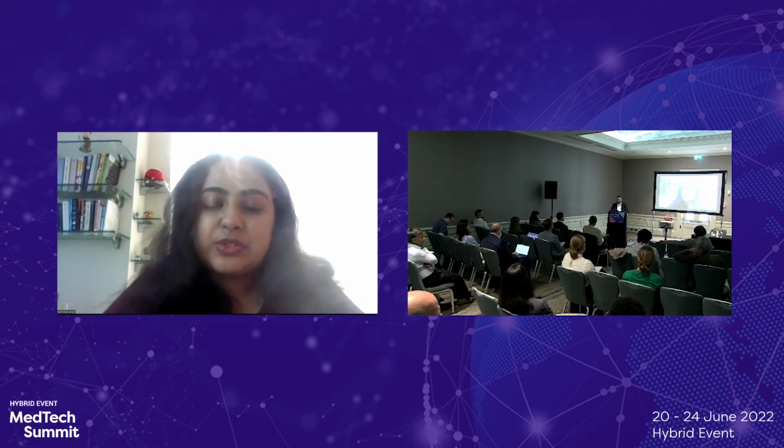Sure. I think, yes, the graphic that I presented can definitely be used as reference. I've prepared that graphic keeping in mind the EU MDR requirements, referring to the MDCG guidances. So you can definitely keep that as your reference point to develop your deliverables. What's one thing to keep in mind though, and I think I previously mentioned, that even though the graphic says that some of the sections are exactly overlapping, for example, your clinical literature or clinical investigation section across the CER and SSCP are overlapping, the requirements are different.